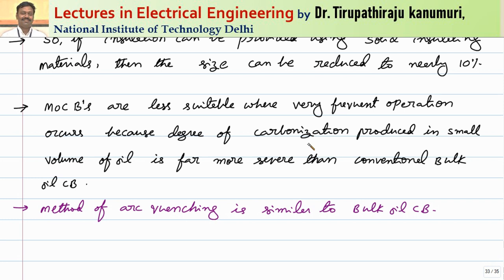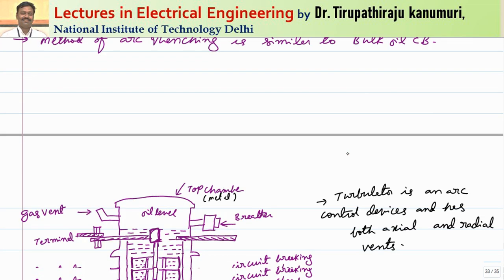The oil gets spoiled at a very fast rate due to carbonization, so frequent maintenance of the oil is required. This breaker cannot be used where frequent operation is required — practically, after every five or six operations you have to check the oil for its dielectric property. Wherever frequent operation is not required, we can go for minimum oil circuit breakers easily. The method of arc quenching is similar to that of the bulk oil circuit breaker.